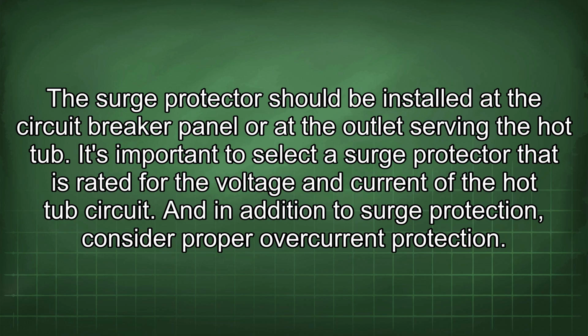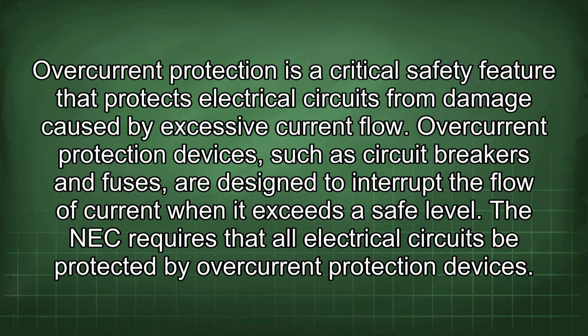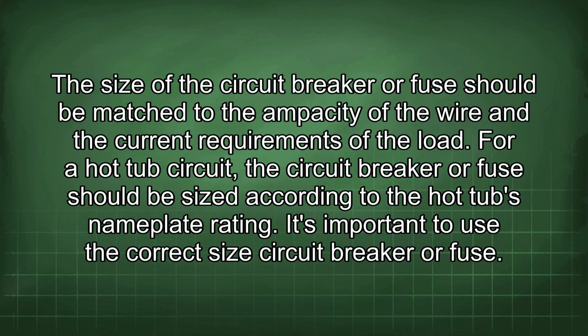And in addition to surge protection, consider proper overcurrent protection. Overcurrent protection is a critical safety feature that protects electrical circuits from damage caused by excessive current flow. Overcurrent protection devices, such as circuit breakers and fuses, are designed to interrupt the flow of current when it exceeds a safe level. The NEC requires that all electrical circuits be protected by overcurrent protection devices. The size of the circuit breaker or fuse should be matched to the ampacity of the wire and the current requirements of the load. For a hot tub circuit, the circuit breaker or fuse should be sized according to the hot tub's nameplate rating. It's important to use the correct size circuit breaker or fuse.